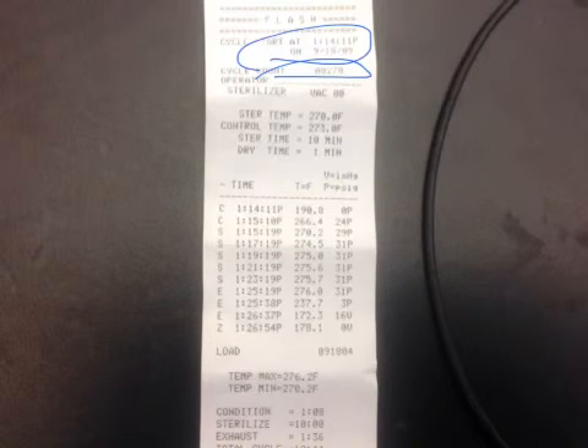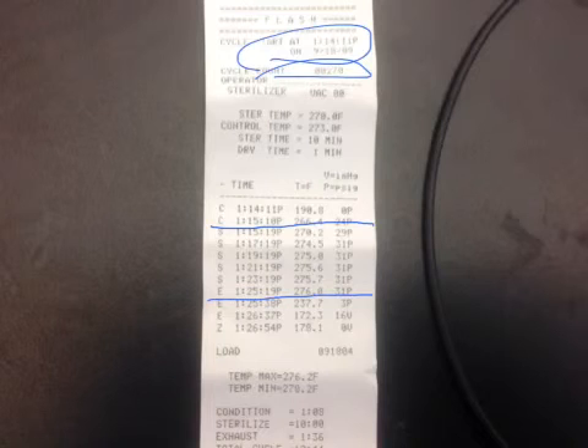So we're going to go down. We see it's conditioning until 1:15:19. So below this blue line is where it starts to sterilize. And it's continuing to sterilize till it reaches 1:25:19.